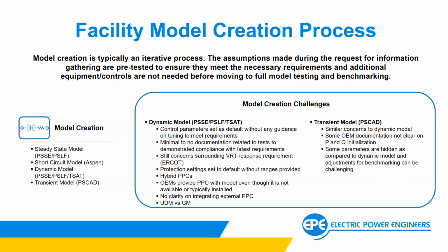I can't say it enough that we get lots of support from the OEMs, and we work with them very closely to go through these processes. But some things that I feel are challenging, that I think we can work closer together with them to give better information, is, like Steven said a moment ago, not being given enough information on XR ratios, et cetera, to give better tunable models. We see that the parameters are set with default values, with minimal guidance on tuning to meet the requirements. And what I mean by minimal guidance is more in the documentation phase, related to some of the tests that are performed during that benchmarking and testing phase.